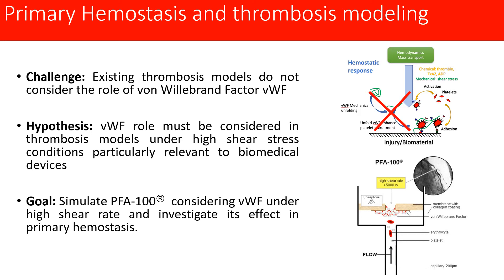The PFA-100 assay consists of sucking blood through a cylindrical cartridge that has a central membrane with an orifice, as shown in the lower right image. When blood is flowing through the orifice, it will occlude, and when this occlusion happens a closure time is obtained that is then used for diagnosis.